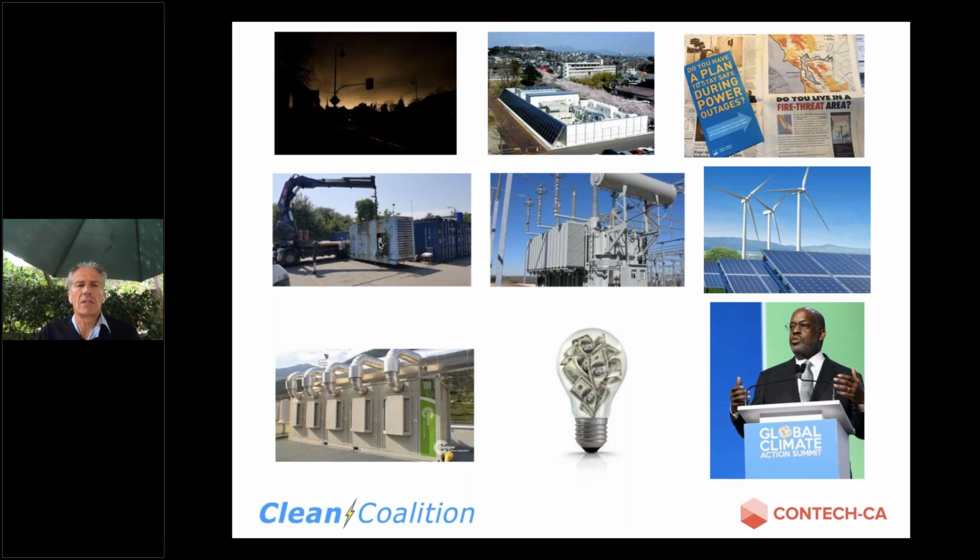The other thing with microgrids, generators. The standard solution to emergency power is a diesel generator, and we use the term stranded asset. Well, when it runs, it's very important, and it provides a lot of value, but it's several $100,000, it needs maintaining, installing, and permitting and designing. It's only really going to give you value in an emergency or a power outage, whereas a microgrid and stored energy solutions can also provide that value ongoing, and also, if it is designed to be able to island in an emergency, provide value in a power outage. We also can better utilize the renewables, save money, and this is also in line with global climate goals and corporate climate goals.